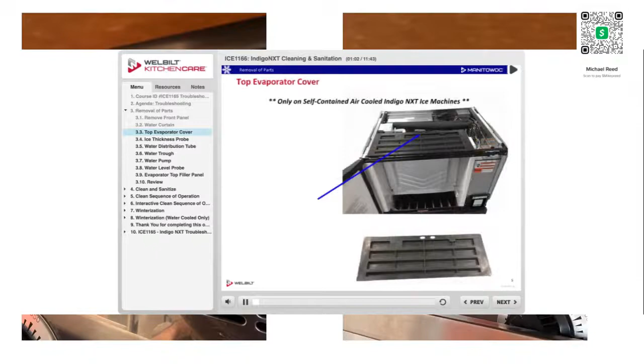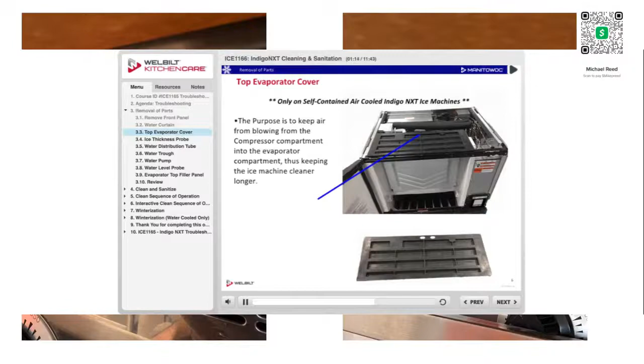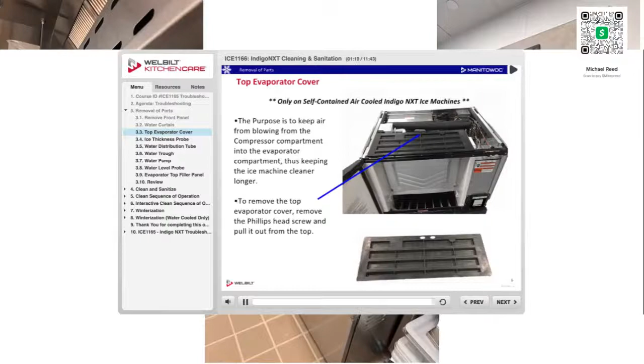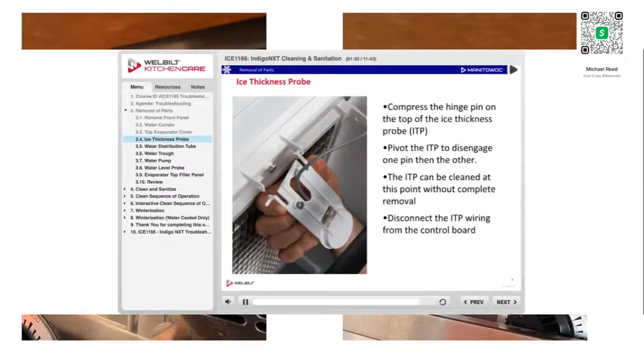Self-contained air-cooled Indigo Next ice machines come with a top evaporator cover. The purpose is to keep air from blowing from the compressor compartment into the evaporator compartment, thus keeping the ice machine cleaner longer. To remove the top evaporator cover, remove the Phillips head screw and pull it out from the top. To remove the ice thickness probe, compress the hinge pin on the top of the ice thickness probe. Pivot the ITP to disengage one pin, then the other. The ice thickness probe can be cleaned at this point without complete removal. Disconnect the ice thickness probe wiring from the control board.